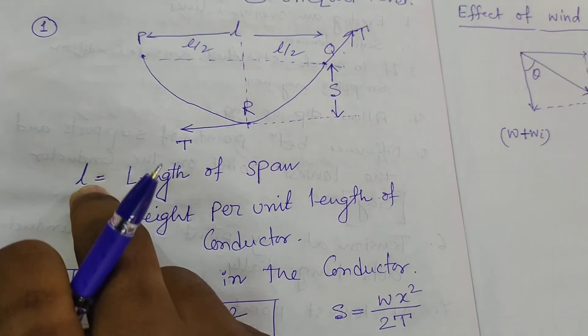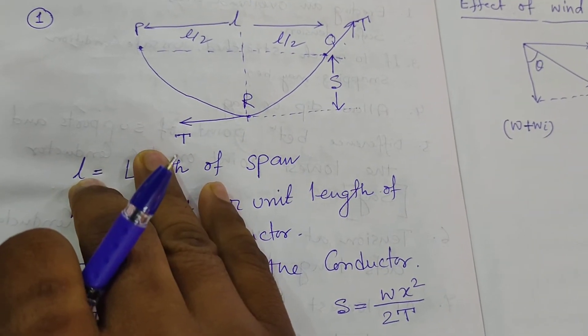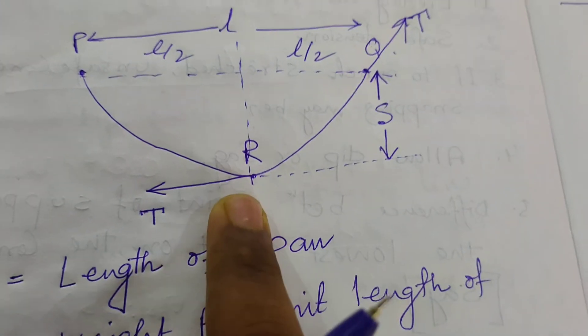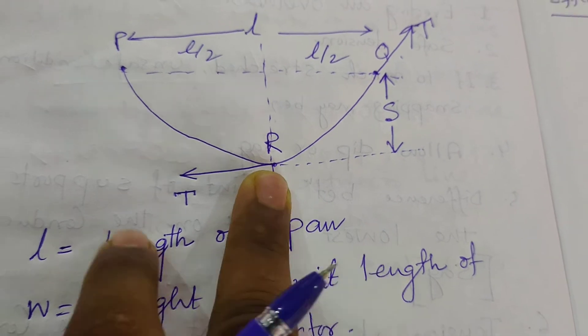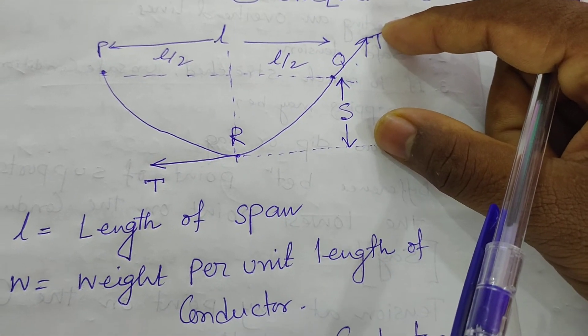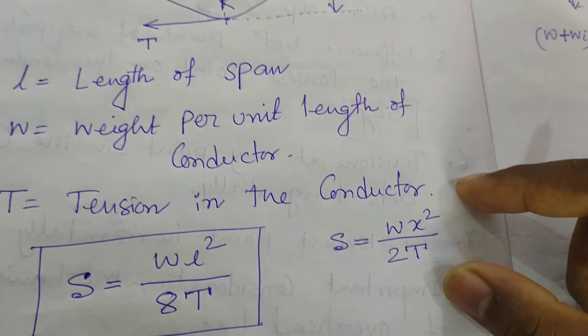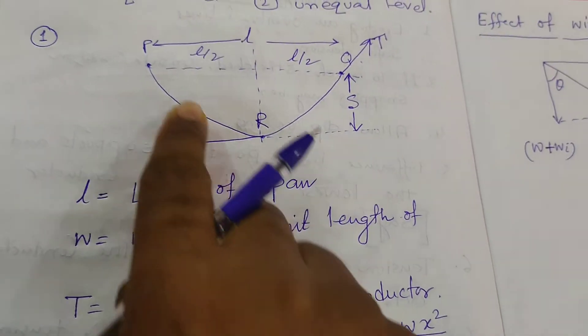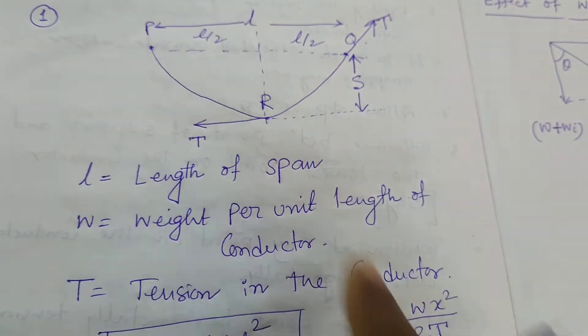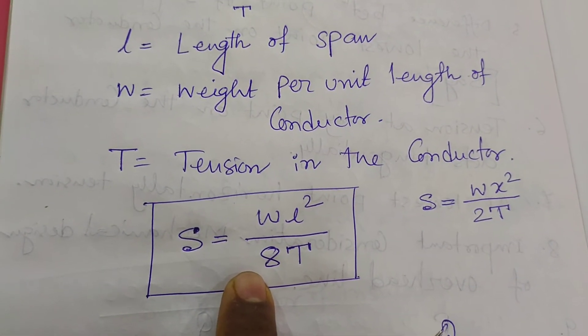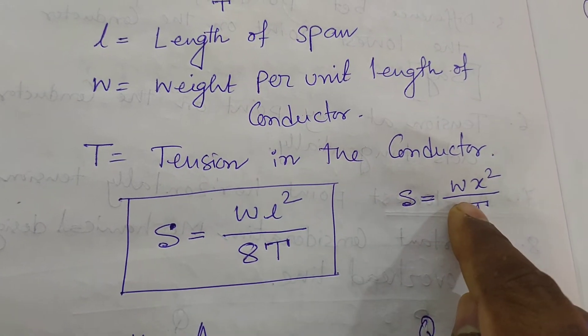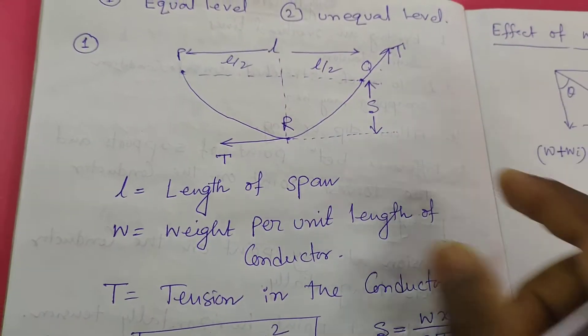We have to consider two points: X and Y. X is the distance from the lowest point, and Y is the SAG at that point. The formula is: Y equal to WX squared by 2T. If we put the condition X equal to L by 2, we get the SAG formula. So you should memorize: S equal to WX squared by 2T, where X is the horizontal distance from the lowest point and Y is the SAG.